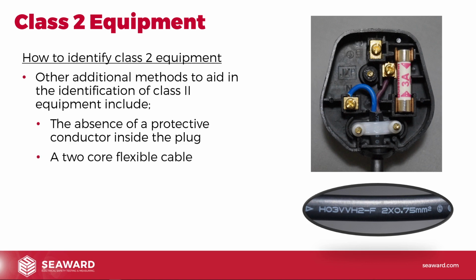There's no earth, and there isn't an earth in there. A 2-core flexible cable. So again, looking at the diagram there of the side of the cable, we can see printed on the side of the cable it says 2 times 0.75. So that's telling us it's a 2-core cable. So even if it's a moulded type plug, we could still look at it, and if it says it's a 2-core cable, as long as that's original cable, you would assume that means it's class 2. It's got the line and the neutral in there and no protective conductor, no earth.